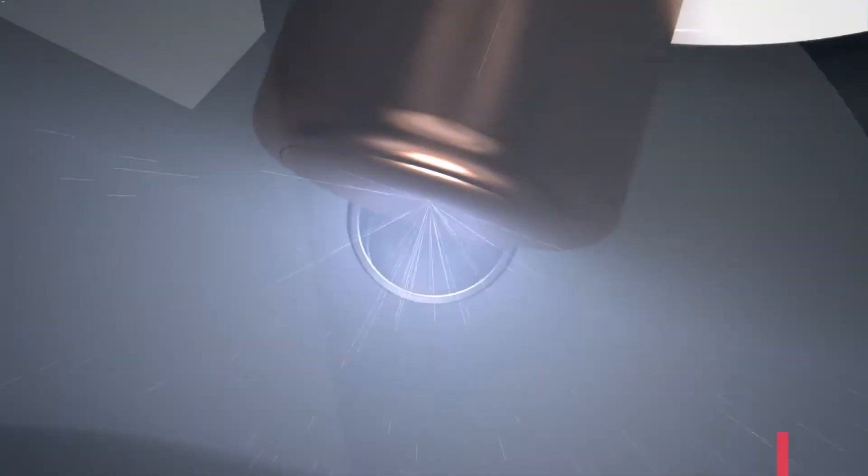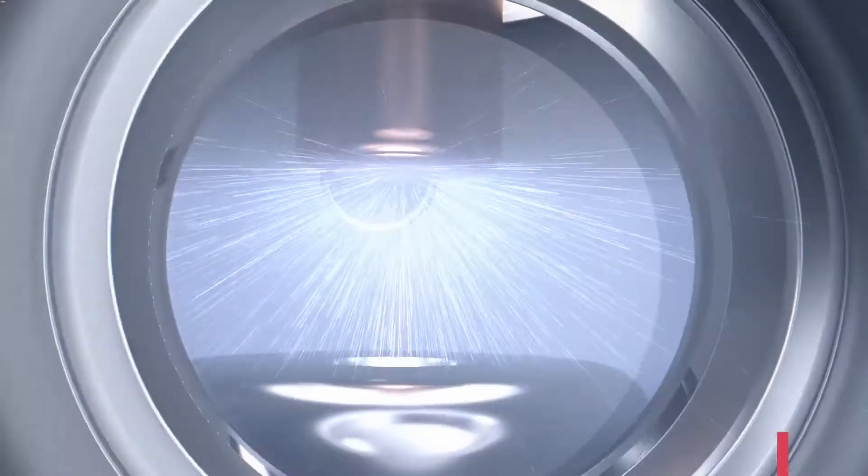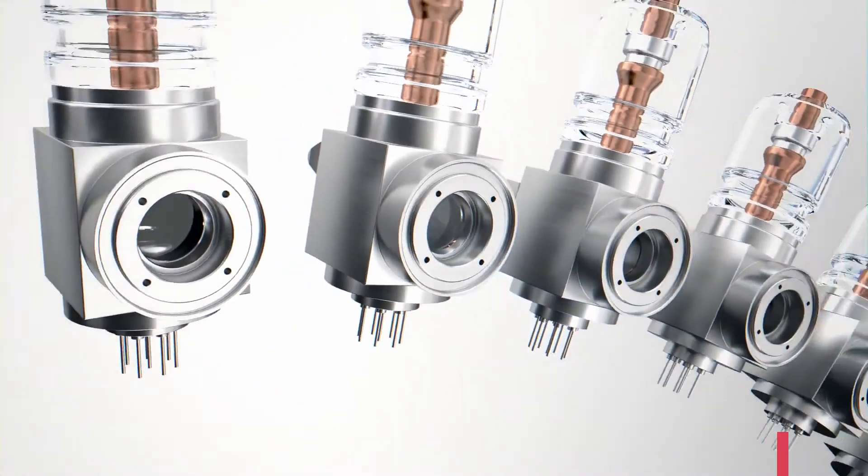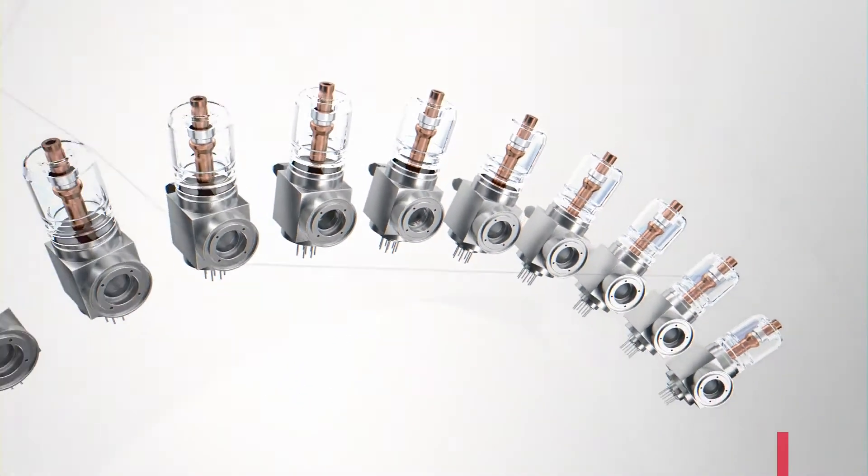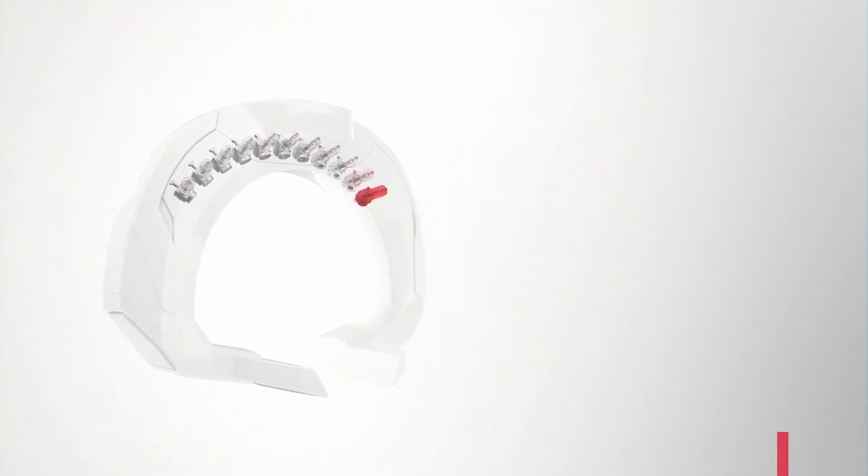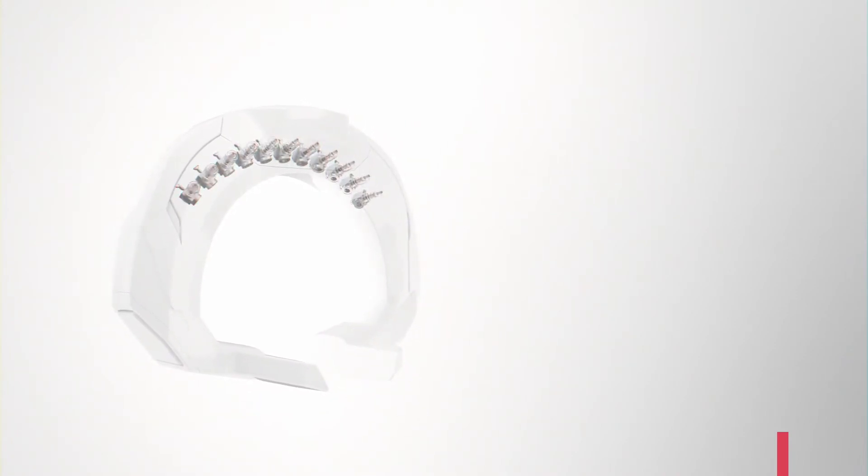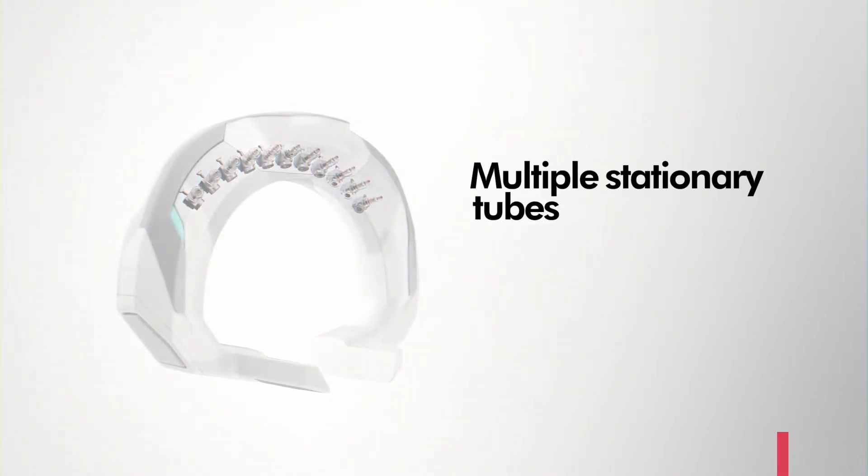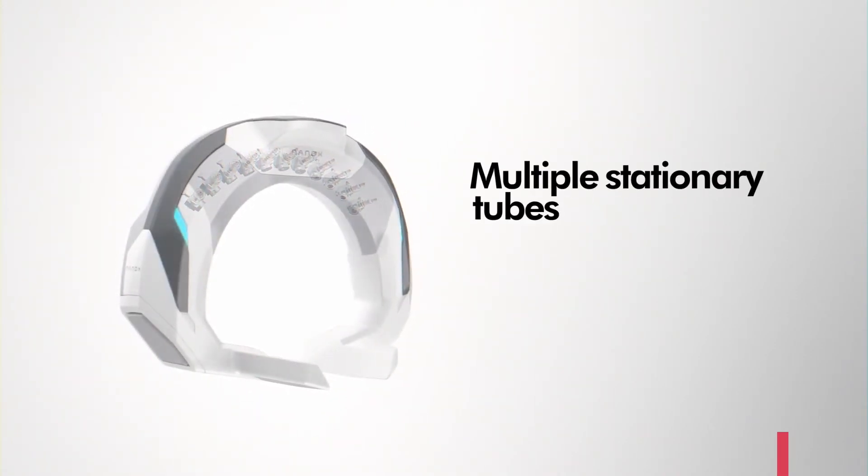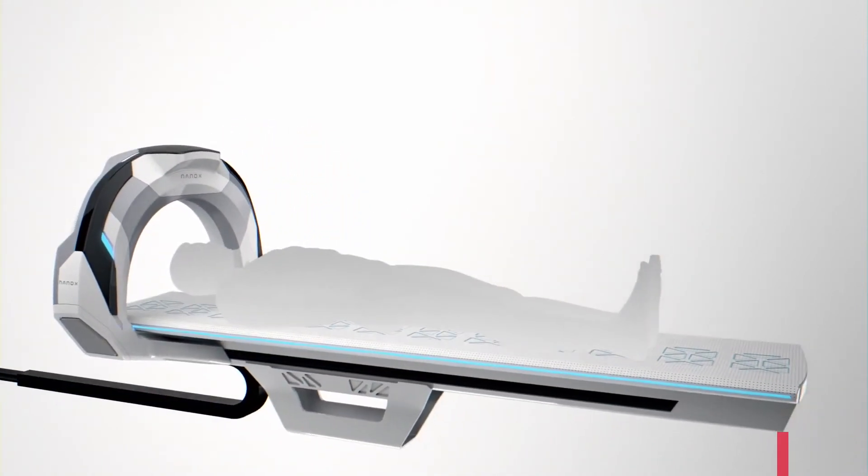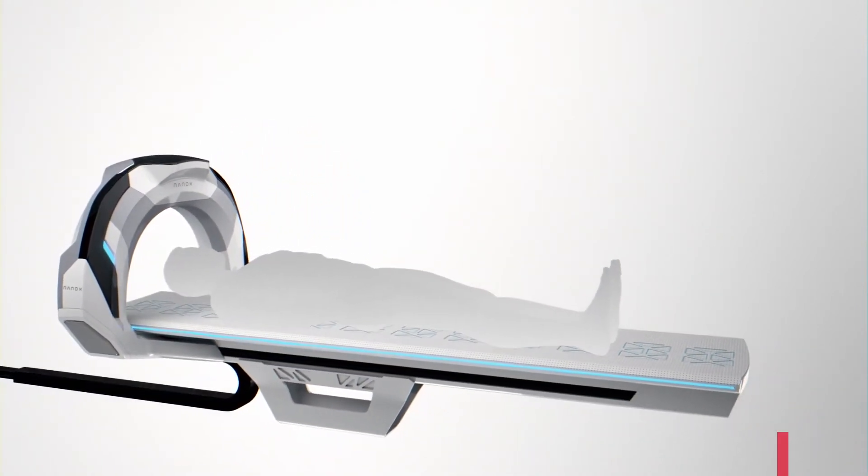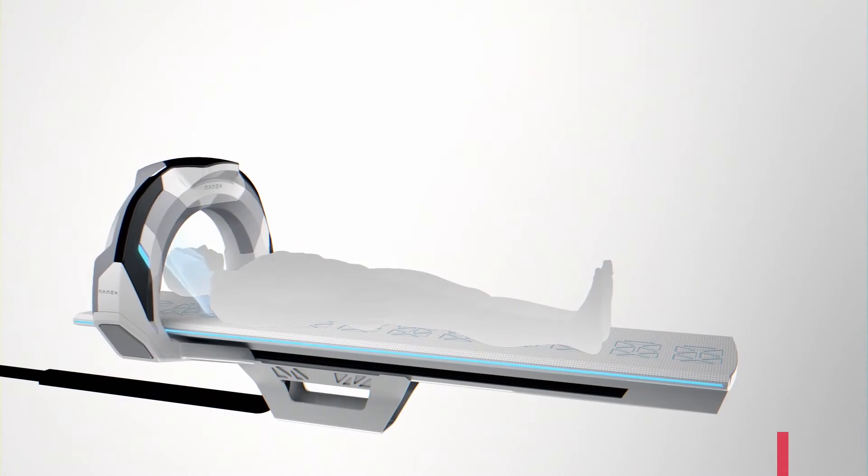Electrons pulsating from each cone hit a different spot on the anode, which also keeps the anode cool without the need to rotate it. The exceptionally small size and low cost of the Nanox x-ray source enables us to construct medical imaging systems using multiple stationary tubes and no moving or rotating parts, thus achieving significant reduction in system size and cost.